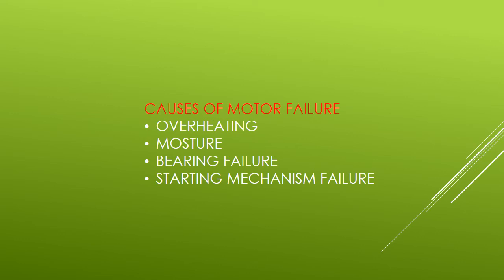Moisture should be kept from entering a motor. Cover the motor to protect it from the weather, particularly during periods when it is not used. Bearing failure. Bearings should be kept properly lubricated. Bearings may seize in unused motors that are not rotated for extended periods. Special care in lubrication may be required for these motors. Starting mechanism failures. Choosing a well-built motor will help solve this problem. The starting mechanism, as well as the bearings and motor windings, must be kept free of dirt and moisture.